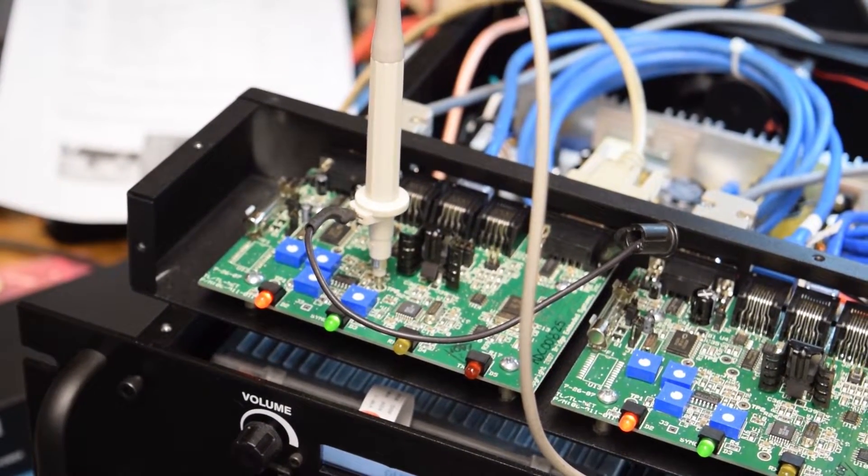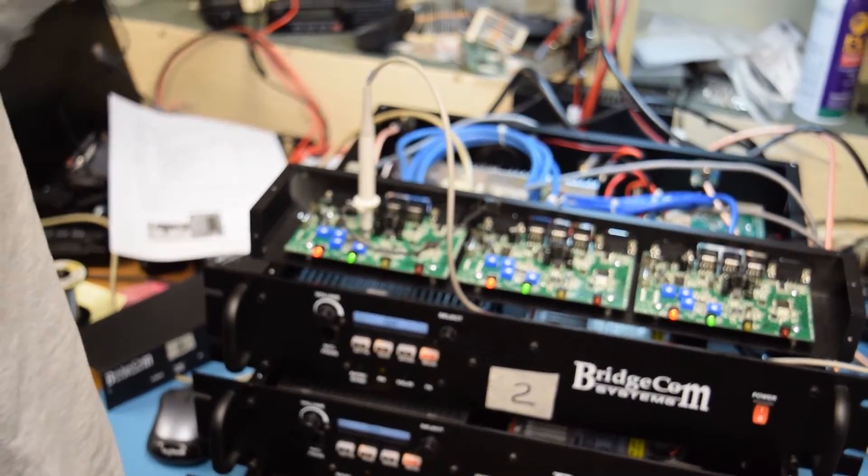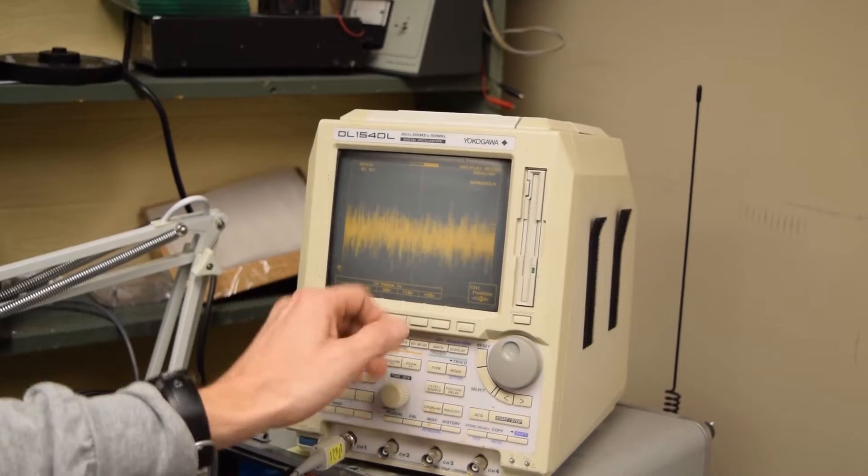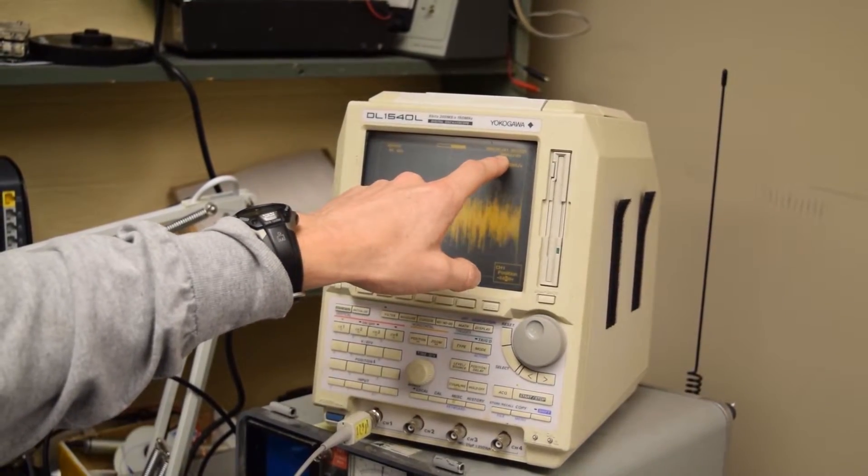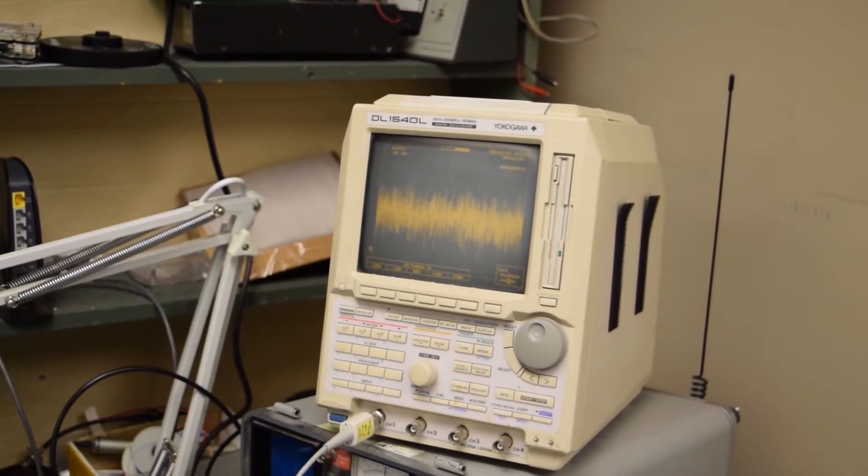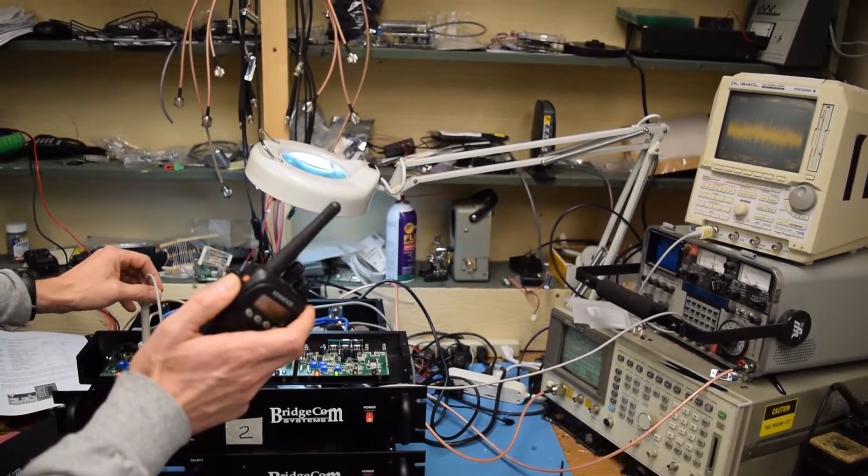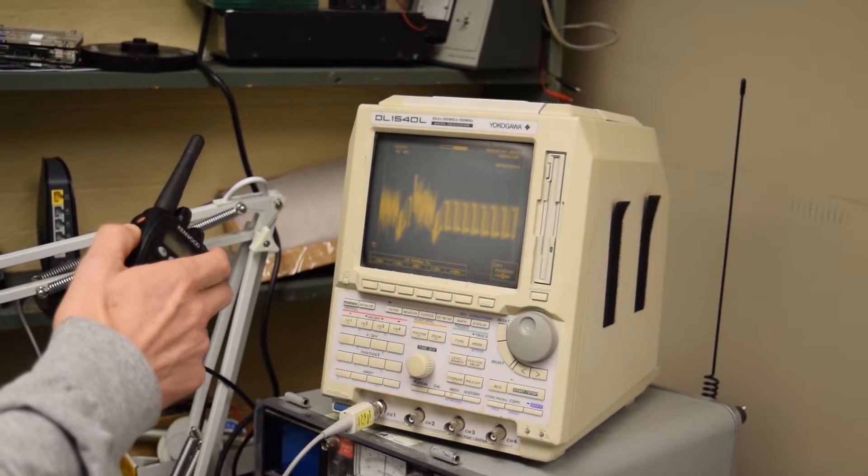The microprocessor has to decode this LTR data, and it has to be of such a level that it can see enough of it. So I've got over here on the oscilloscope what that signal's looking like. I've got it set up for a couple hundred millivolts per division, and one volt, I'm sorry, a sweep speed of 200 milliseconds and one volt per division. So I'm going to actually handshake with the controller number two, and I wanted you to see what this looks like from the receive side. So you'll notice this data coming in.